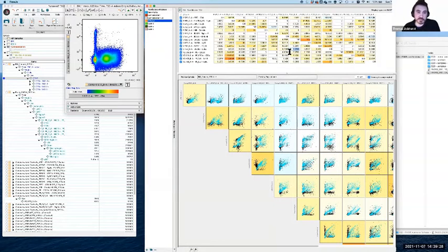Now, the value is much the same as we talked about before. The actual value here, in case you can't read it, is 0.0781. So it's a very low compensation value. So it's effectively 0. Just to give you an idea of what happens here, if I set this to 0, it's probably not going to move very much, but it might move a tiny bit. Yeah, it's pretty much no movement.